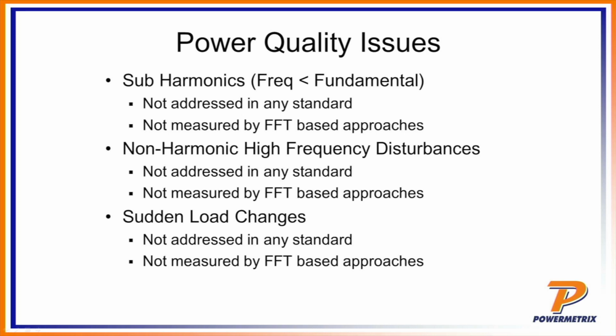And the last thing is sudden load change. Sometimes if you have a really, really sharp transition in your load, that can, once again, generate some high levels of harmonics. Not being addressed in any standards, and once again, may not be caught by your FFT. Really depends on the sampling rate of the meter as to whether or not that would be caught or not.